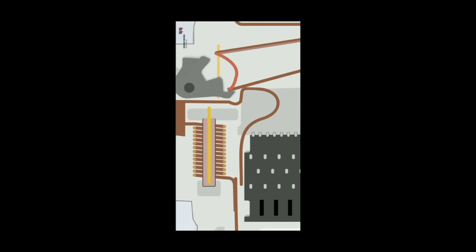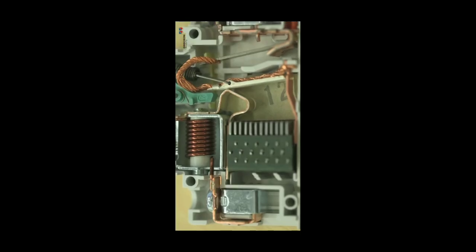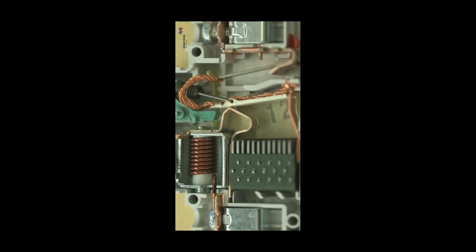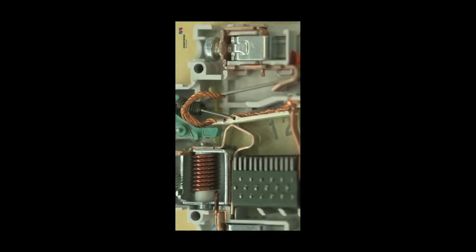Due to magnetic forces, the arc moves through a stack of metal plates where it is cooled, split, and finally extinguished at the next zero crossing. Despite its small size, an MCB has a rather sophisticated design, consisting of 2 separate tripping mechanisms for overloads and short circuits. The quality of the materials used by the manufacturers differs widely.